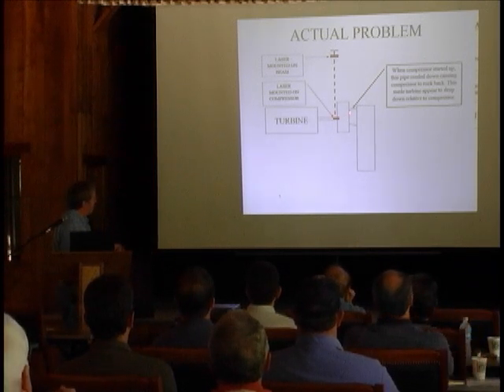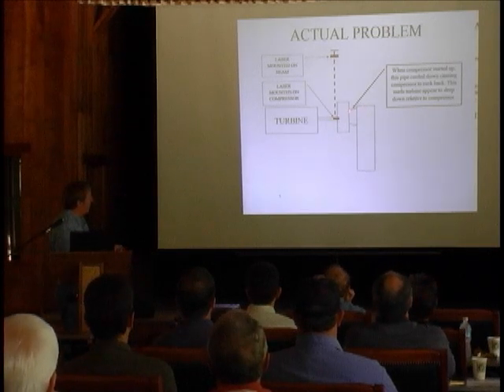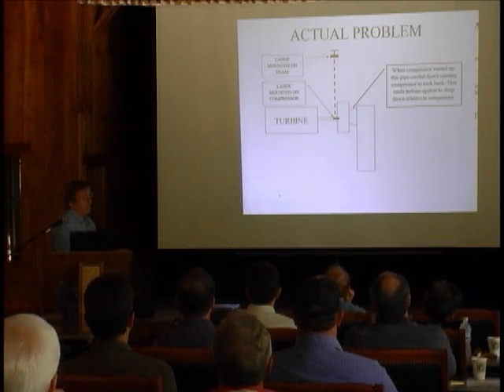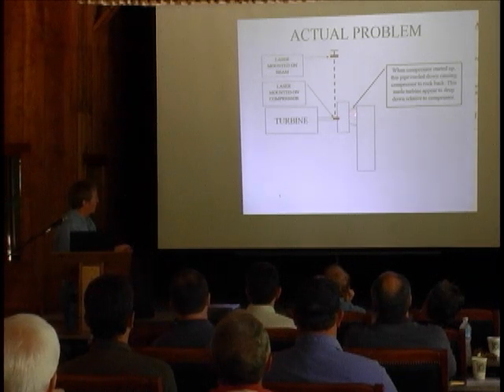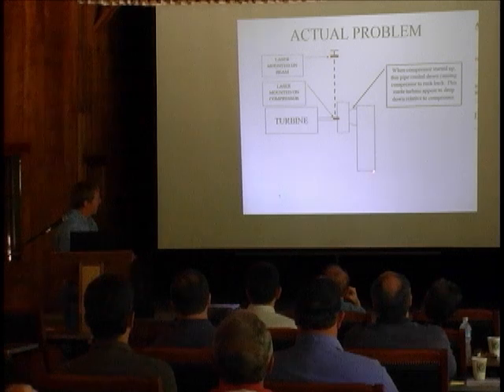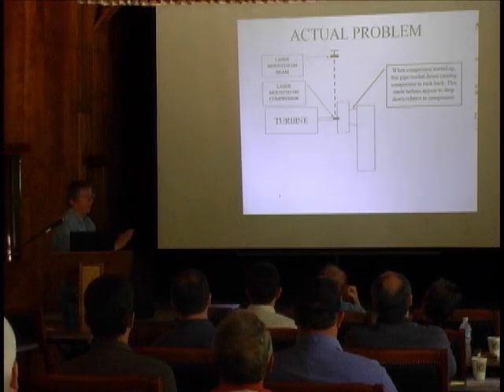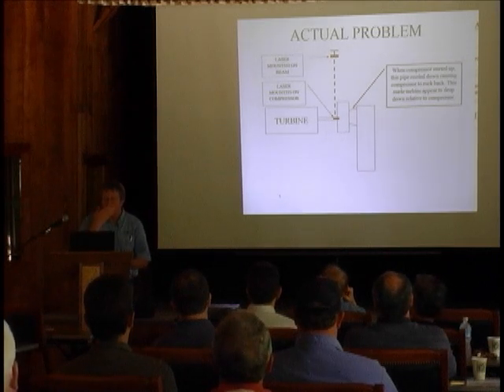Anyway, I wondered what was happening, and then I found there's this huge heat exchanger here, and then there was this pipe here which didn't have an expansion joint in it, and because it was a chiller, this pipe would chill down to very low temperatures. So when this shrunk, that would pull this compressor backwards, because this heat exchanger was 10 times as big, it wasn't moving. And it's very repeatable. Every time it did the same thing.